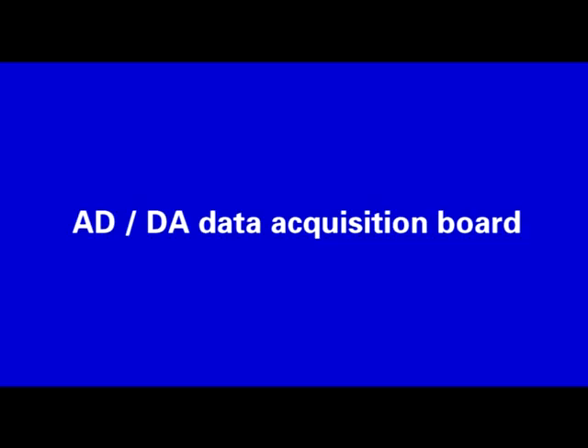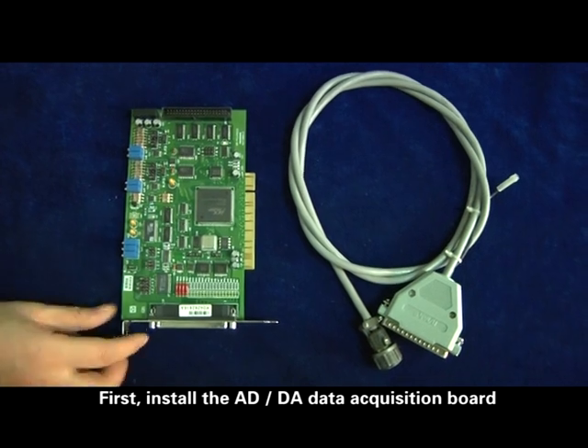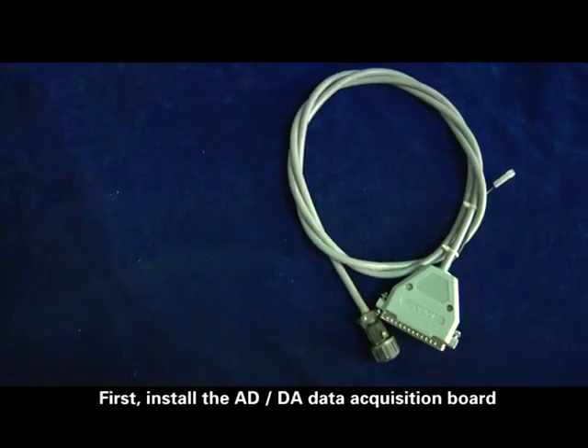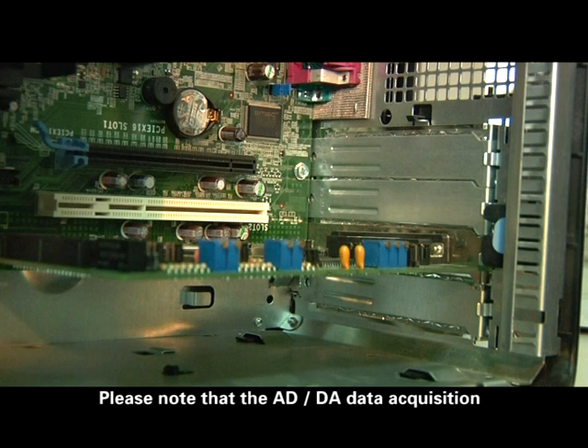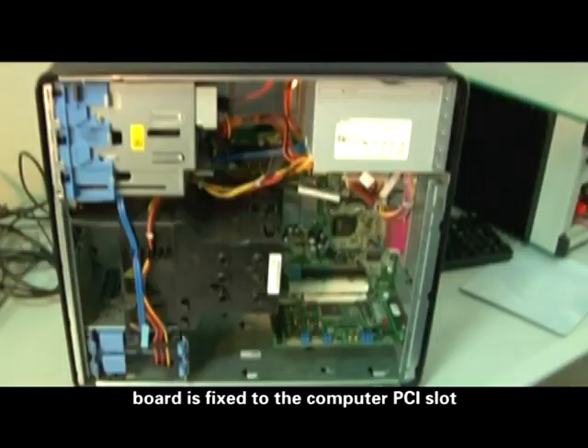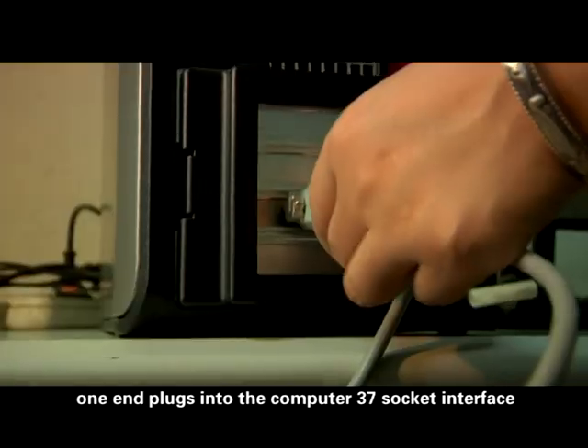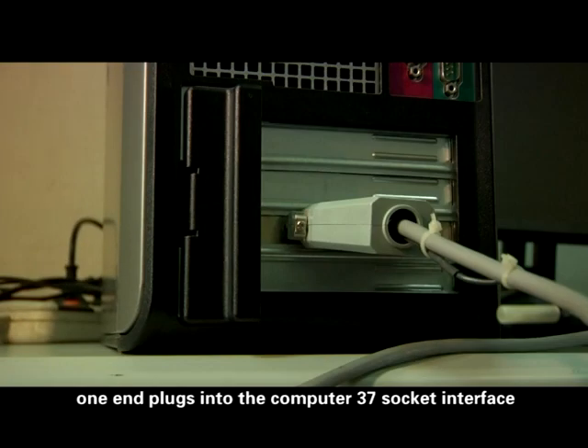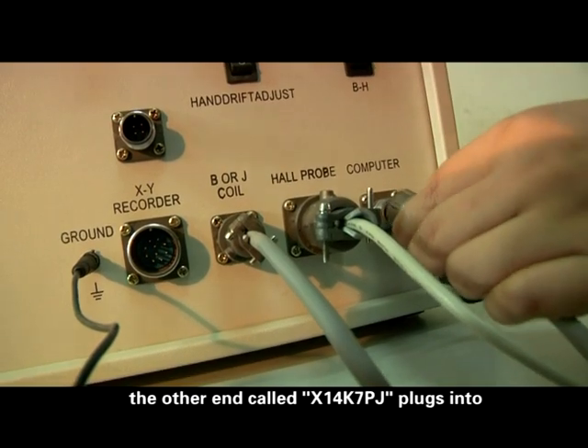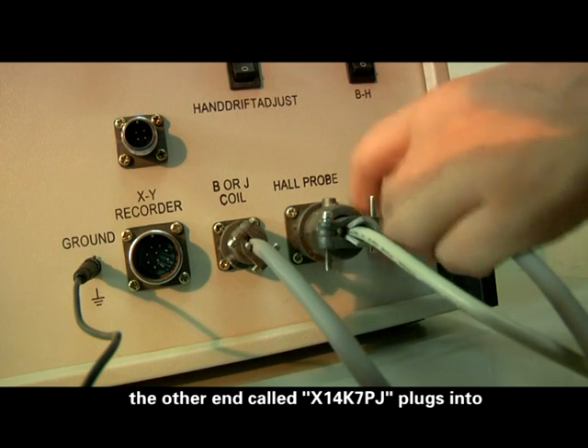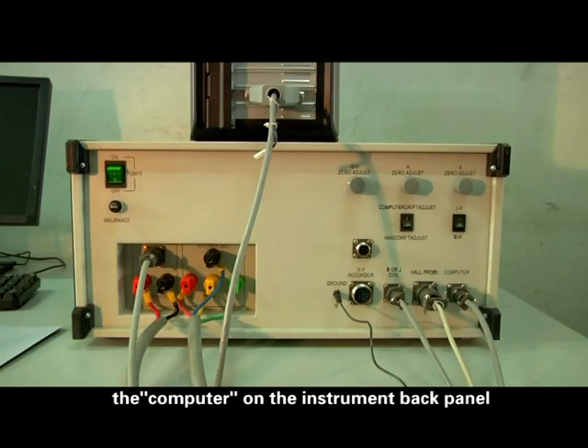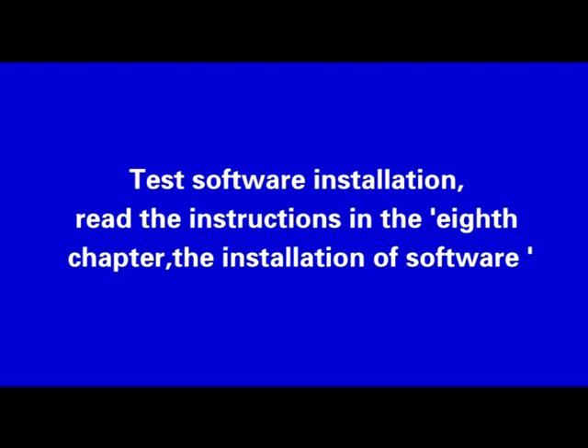ADDA data acquisition board. First, install the ADDA data acquisition board. Please note that the ADDA data acquisition board is fixed to the computer PCI slot. ADDA data lines connection. One end plugs into the computer 37 socket interface. The other end, called X14K7PJ, plugs into the computer on the instrument back panel. Test the software installation. Read the instructions in the 8th chapter, the installation of software.